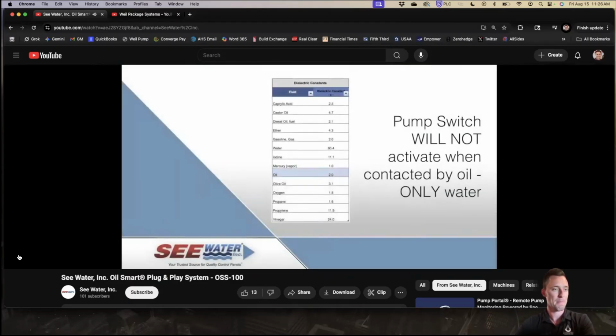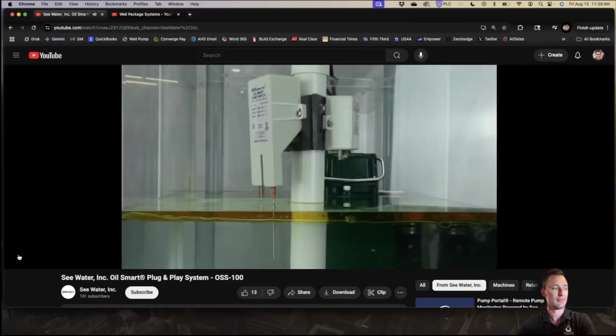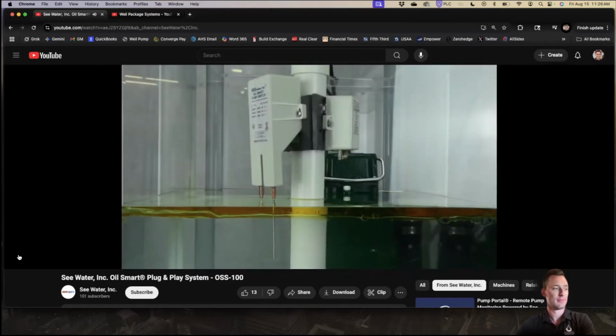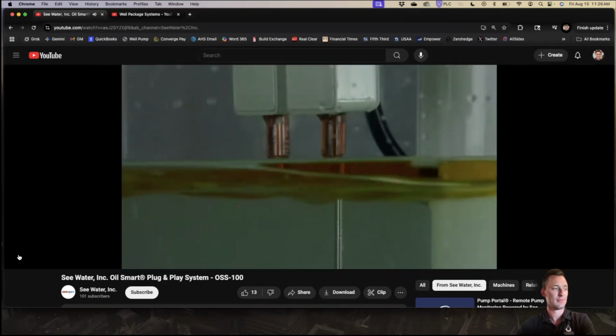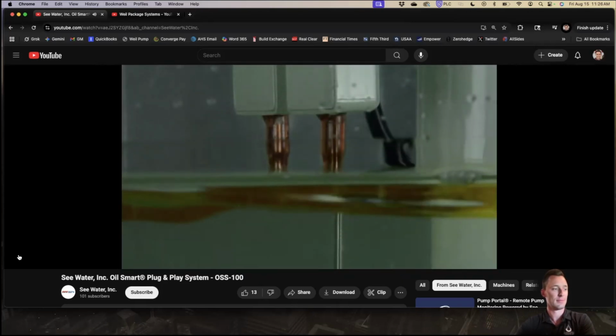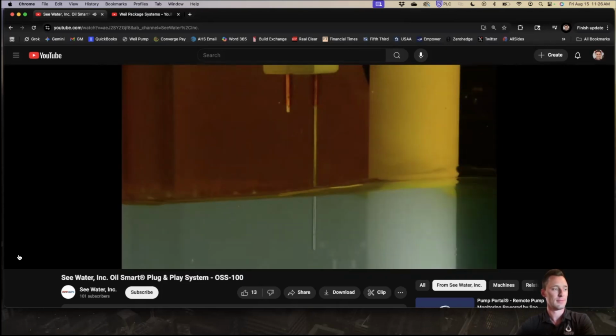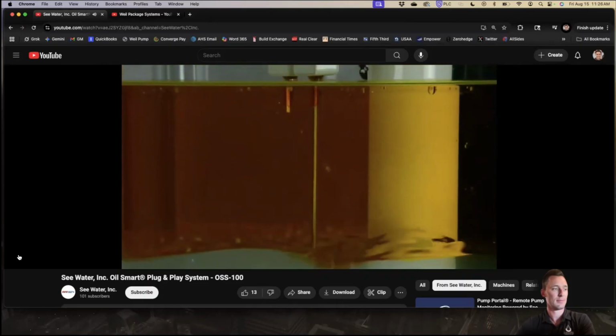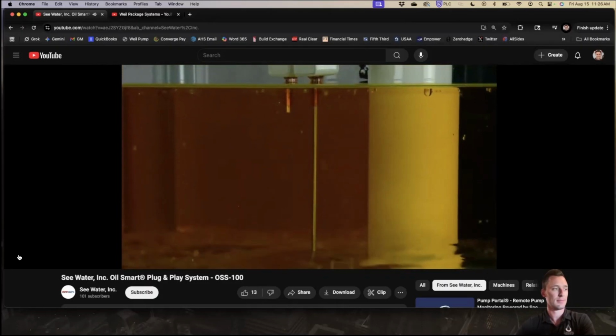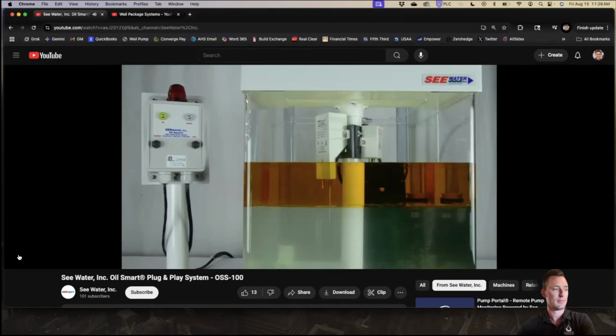Due to the low dielectric value of oil, the pump will not activate when oil comes in contact with the on sensor. However, if the pump controller detects a field of water under the oil, the pump will activate and pump the water out from under the oil, stopping the pumping process prior to pumping any oil.